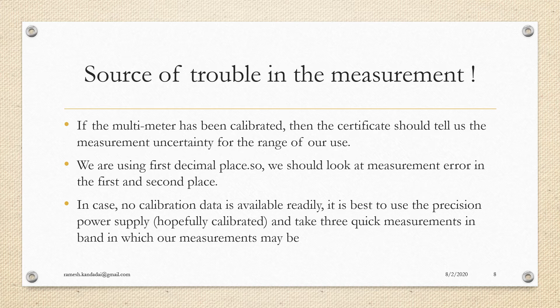If a calibration has been done, typically there would be a certificate available that says the measurement uncertainty is so much. If we are measuring up to the first decimal place, then we will probably calibrate to the second decimal place. In case no calibration data is available, we can quickly check the meter by taking the precision power supply, which is hopefully calibrated, and take 3 quick measurements and do a linear regression on it.